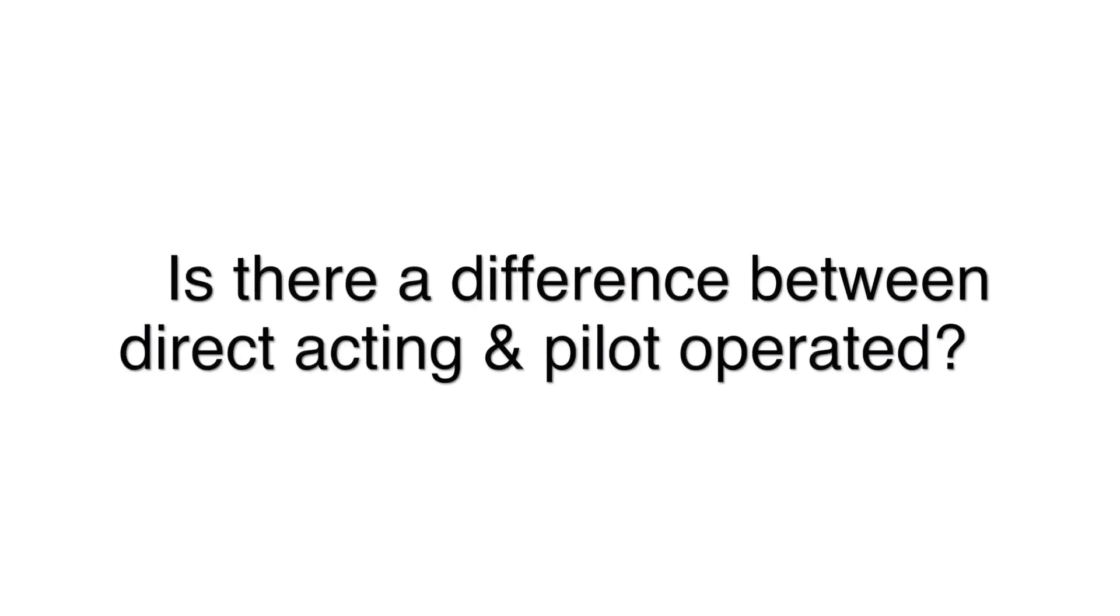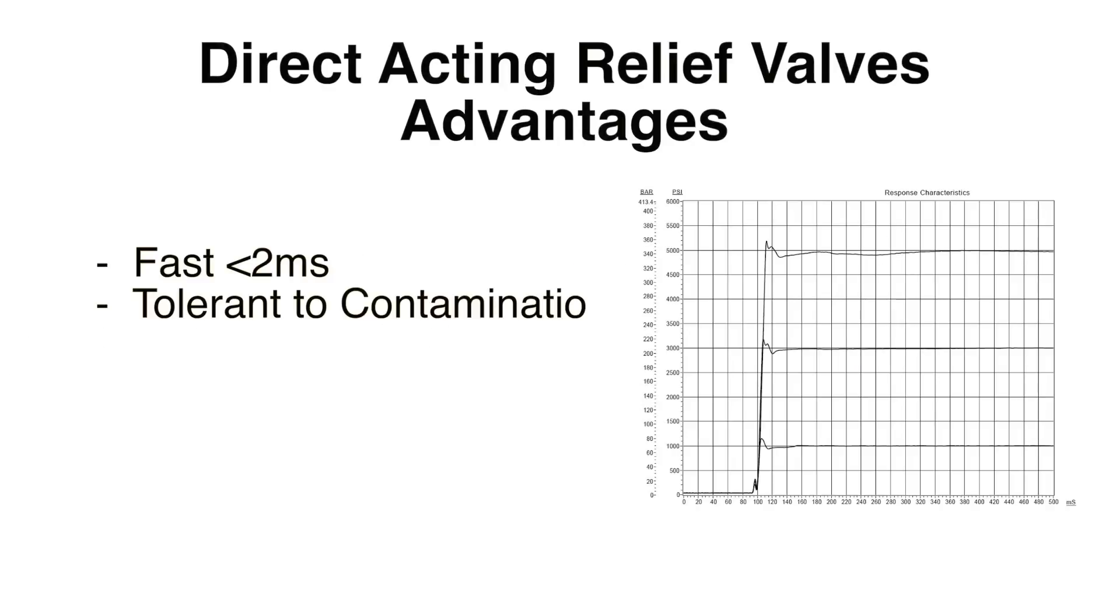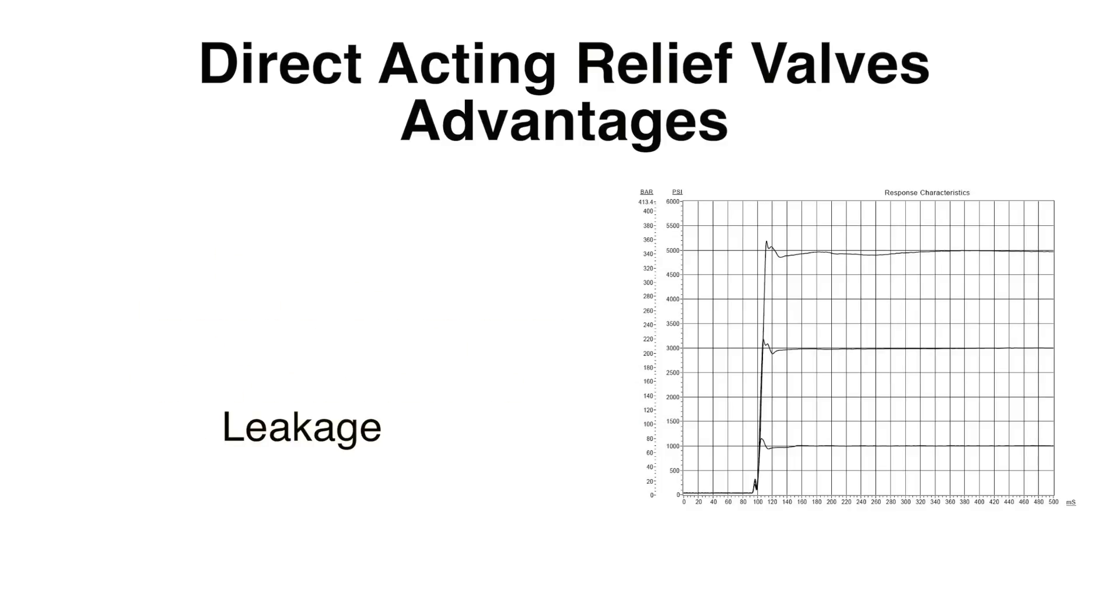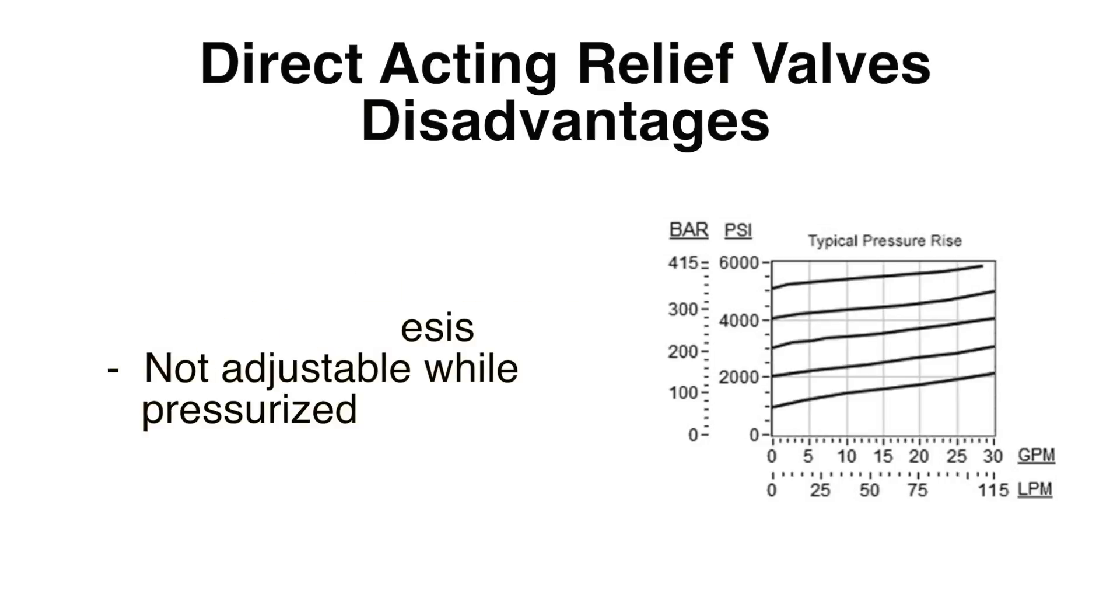Why the difference? There are advantages and disadvantages to each type. Direct acting valves are very fast, responding in sub-2 milliseconds. They're also tolerant to contamination and exhibit very low leakage rates. However, there are some challenges: they have high override pressure, higher hysteresis, and are not adjustable while pressurized.